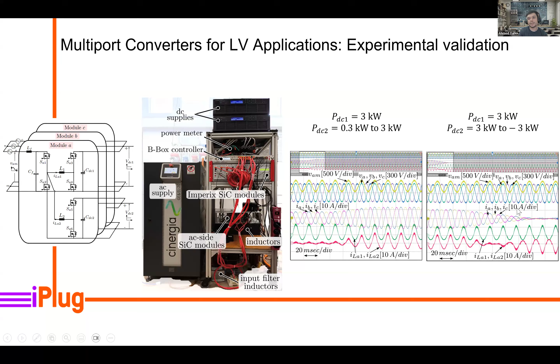We tested this in different scenarios, including steady state and transient. Here we do a step change in one of the boards while the other is fixed, to demonstrate full decoupling between boards. Also in this scenario, we do a step change from rectification to inversion: the grid is supplying the two DC boards, but when one of the boards, instead of consuming power, injects power to the other board, there is almost no contribution from the AC grid, and the DC boards exchange power between themselves.